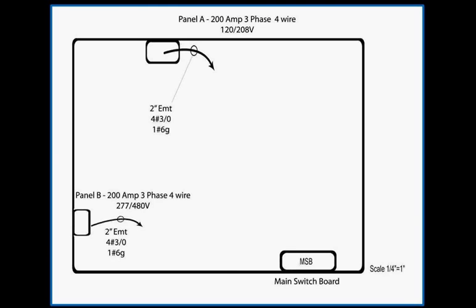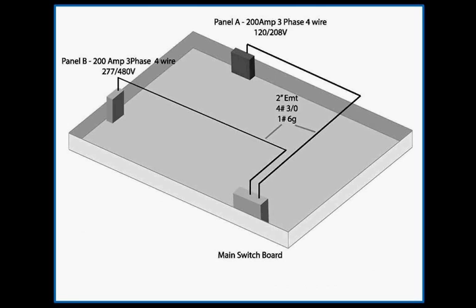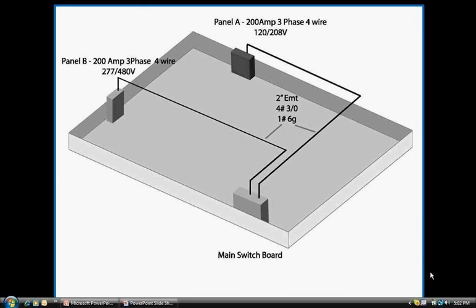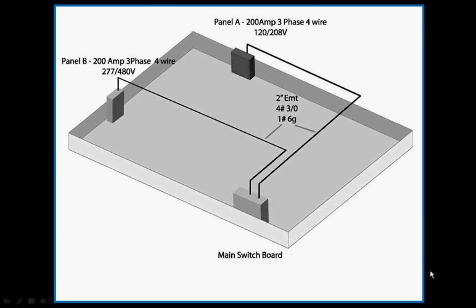To better understand what the two-dimensional drawing represents, I'll also use a three-dimensional drawing of the same building. This is not the view you would normally have on blueprints, but it shows how the conduits run out of the top of panel MSB over and back down into panels A and B. I will also use this drawing to illustrate three things you should be familiar with: conduit risers, elbows, and wire makeup.